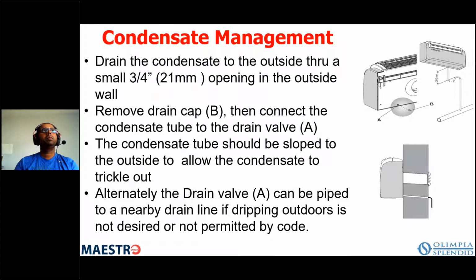Now, if you live in South Florida, Louisiana, or around there, they have so much humidity that you'd probably still have some coming out, because you can only use so much of it. And another thing to bear in mind is in the wintertime, we don't use that pump, because we can't use the pump to pump the condensate onto the outdoor coil, which is now the evaporator. So in the wintertime, we have to be able to drain the condensate that comes as a part of the defrost cycle. But question? Yes, sir.